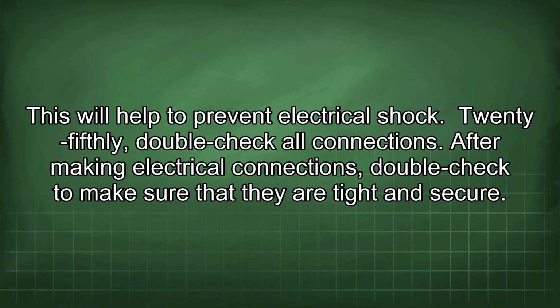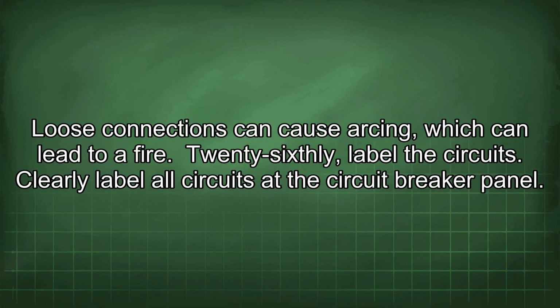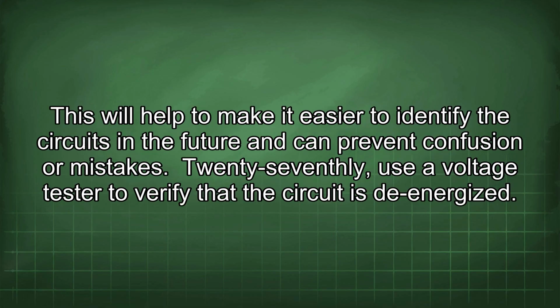25thly, double-check all connections. After making electrical connections, double-check to make sure that they are tight and secure. Loose connections can cause arcing, which can lead to a fire. 26thly, label the circuits. Clearly label all circuits at the circuit breaker panel. This will help to make it easier to identify the circuits in the future and can prevent confusion or mistakes.